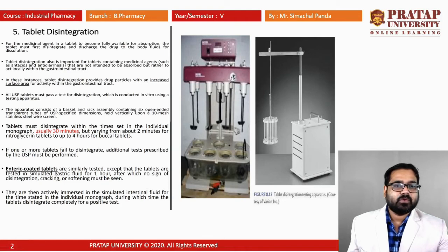That is equivalent to our body temperature. The tablet is placed inside, with the downside closed with the mesh, and above it we place one disc that can apply some pressure. Whenever it is moving to and fro, it gives some pressure, which is equivalent to the peristaltic movement of our GIT. Due to that, the tablet moves up and down, and the time required to break the tablet so that it crosses the 10 mesh sieve is known as the disintegration time.